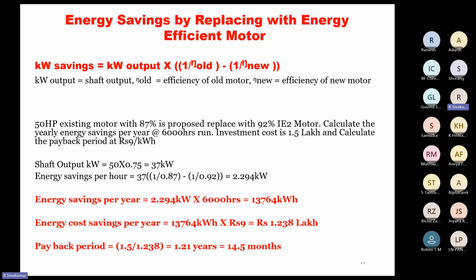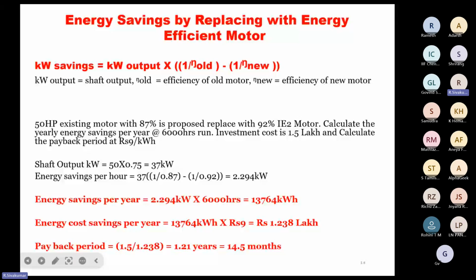So the investment cost is 1.5 lakh, and the payback period is calculated for an operating electricity cost of 9 rupees per unit. By replacing the existing motor with the new motor, we can save almost 2.294 units per hour. If the motor is running for 6,000 hours, that means 13,764 units can be saved in a year. The equivalent cost is 1.24 lakhs.